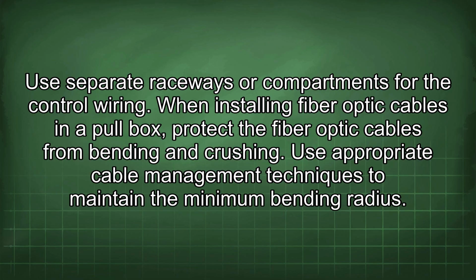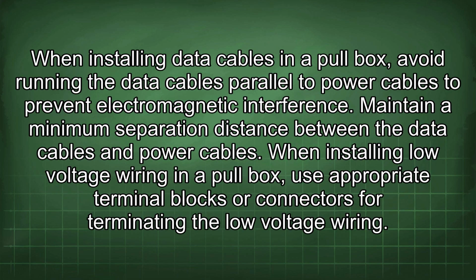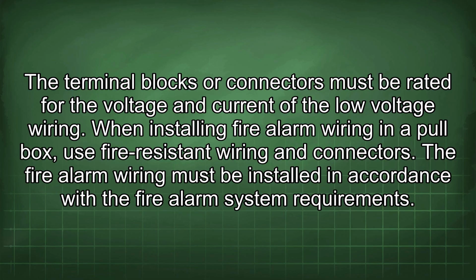When installing fiber optic cables in a pull box, protect the fiber optic cables from bending and crushing. Use appropriate cable management techniques to maintain the minimum bending radius. When installing data cables in a pull box, avoid running the data cables parallel to power cables to prevent electromagnetic interference. Maintain a minimum separation distance between the data cables and power cables. When installing low-voltage wiring in a pull box, use appropriate terminal blocks or connectors for terminating the low-voltage wiring. The terminal blocks or connectors must be rated for the voltage and current of the low-voltage wiring.